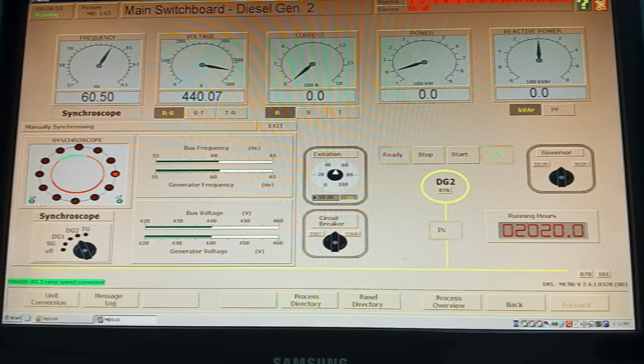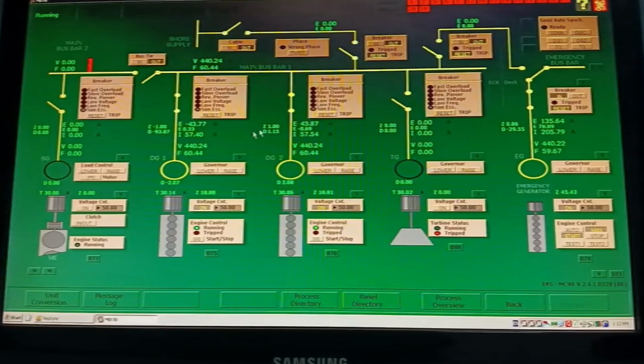So you can see at delta V and delta F, both these lights should be on to indicate that synchronization has happened. So both voltage and frequency are same. So when it reached 11 o'clock, I connected the circuit breaker. So if you check your electric power plant, both generators would have connected and both would have synchronized.